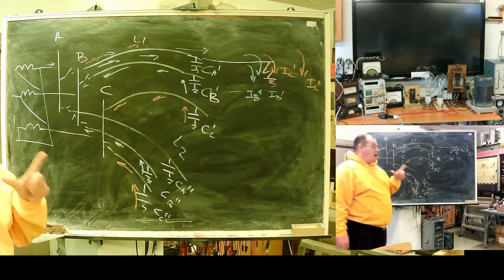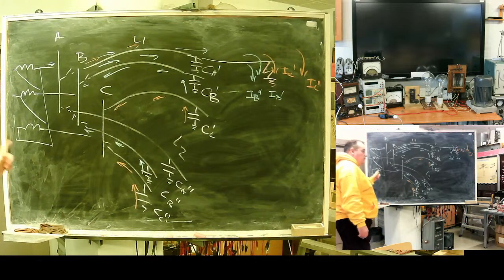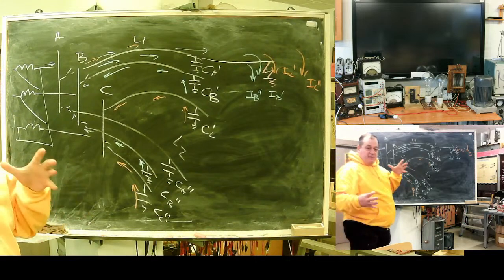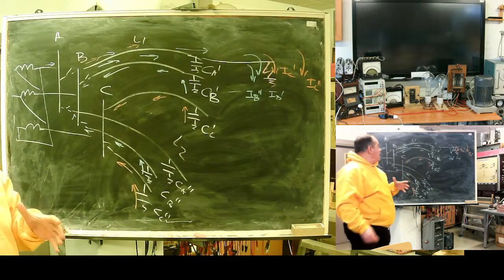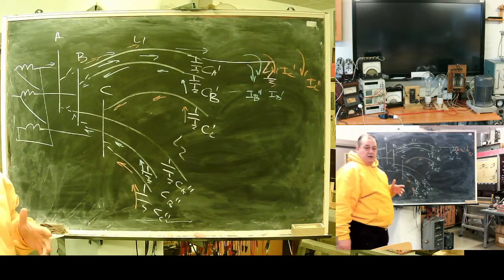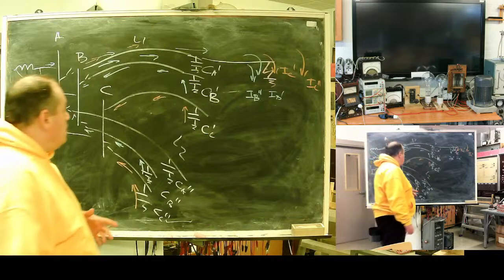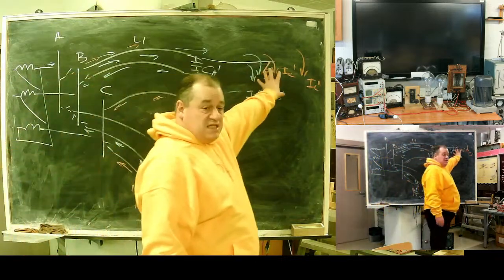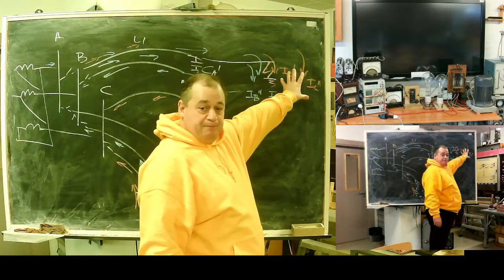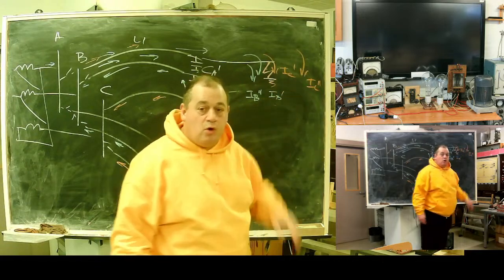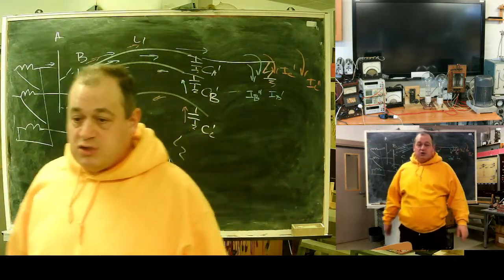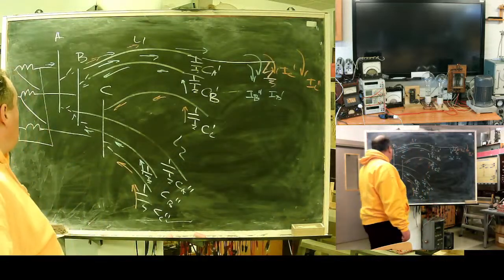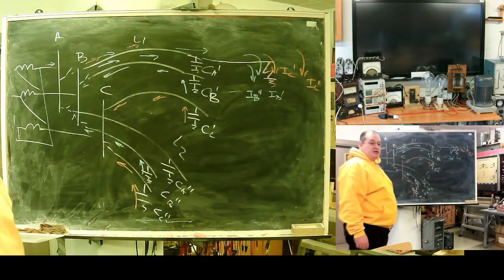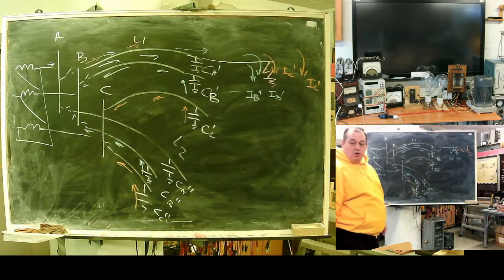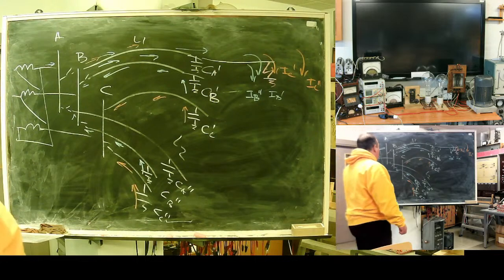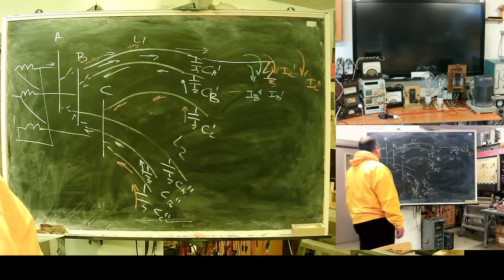Do I need to take some current, some signal for my protection? Can I use phase current? No. All this is in some, let's say, 15 amps. Load current, 1000, 2000, so I will see nothing. I need to take a zero sequence. The only choice for me is to analyze zero sequence current.